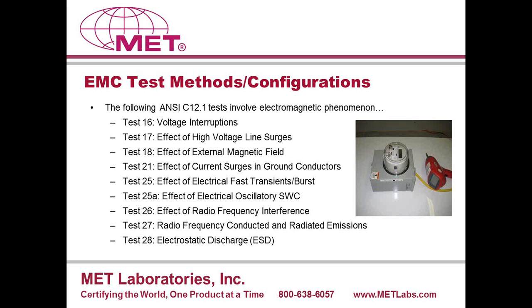Test number 16 is voltage interruptions. Voltage interruptions are caused because of faults in the network or when there is a sudden large change in the load. Test number 17 is effect of high voltage line surges. This test is performed to determine the surge withstand capability of an equipment that will be exposed to known or unknown surge environments. The major concern here is either switching induced or lightning induced transients, which will give rise to either a ring wave or a combination wave pattern. This test is usually performed at 6,000 volts, or 6 kilovolts.